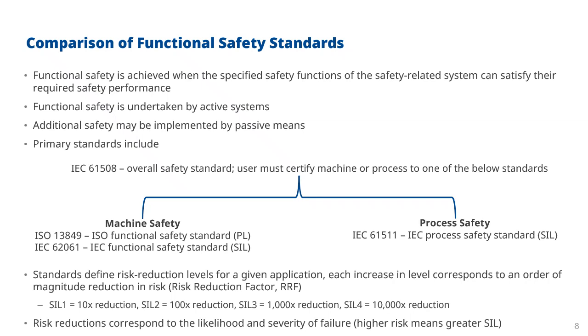I also hear of other trends though, where people are looking to reduce to things like maintenance operations. So for example, one way you might get down from SIL 3 to SIL 2 is by having more regular inspections, but because it's an unmanned operation, that means you have to shut the plant down while you're performing the inspection. So that affects your availability. So some people are looking to increase from SIL 2 to SIL 3 because they want to reduce the amount of time the plant is down. So that means they have to work for longer between the different operations where no one is present. So there's different standards and there's different requirements that apply, and different users will have different ideas of what they need. But again, they have to decide what level of functional safety they need, and that needs to be based on a defined methodology, typically by performing this functional safety assessment.